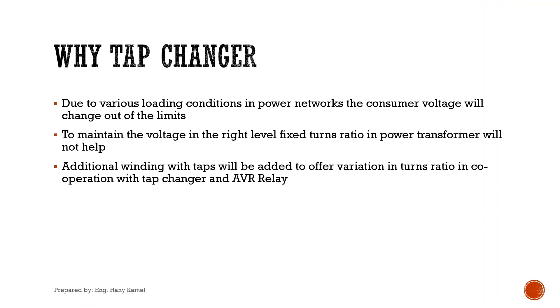Why tap changer? Due to various loading conditions in power networks, the consumer voltage will change out of the limits. To maintain the voltage at the right level, a fixed turns ratio in a power transformer will not help. Additional winding with taps will be added to offer variation in turns ratio, in cooperation with the tap changer and AVR relay.